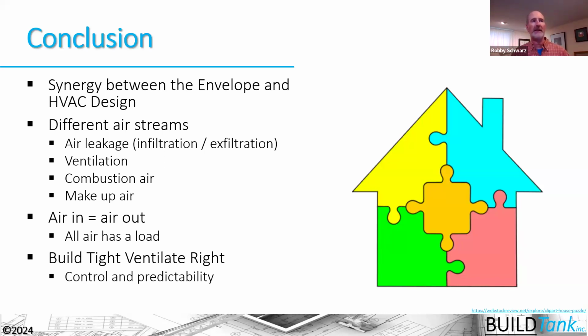We need to think about the different air streams, and that the air leakage, the infiltration, the exfiltration are uncontrolled, accidental air movement through our building envelope. Whereas ventilation is controlled and predictable airflow through the building envelope. Yes, we might not know exactly where the holes are, but we know that when we put it on a schedule and we use a fan to move that air, that we have greater control and predictability.